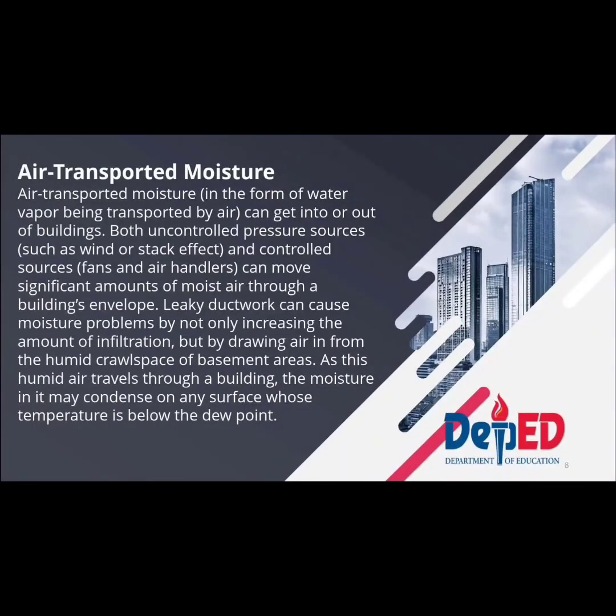Air-transported moisture. Air-transported moisture, in the form of water vapor being transported by air, can get into or out of buildings. Both uncontrolled pressure sources such as wind or stack effect and controlled sources such as fans and air handlers can move significant amounts of moist air through a building's envelope. Leaky ductwork can cause moisture problems by not only increasing the amount of infiltration, but by drawing air in from the humid crawl space or basement areas.